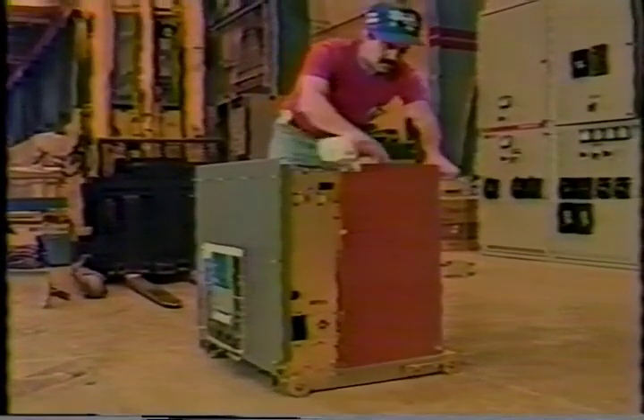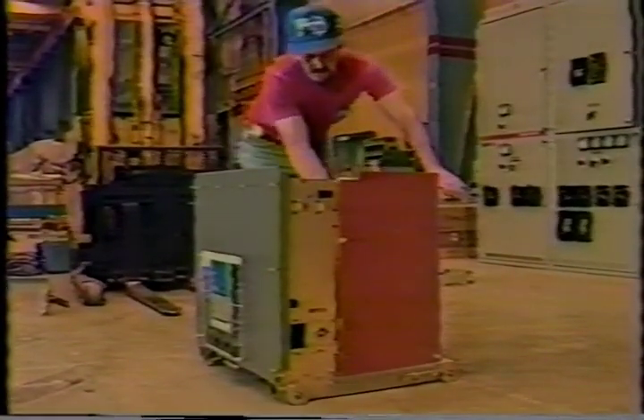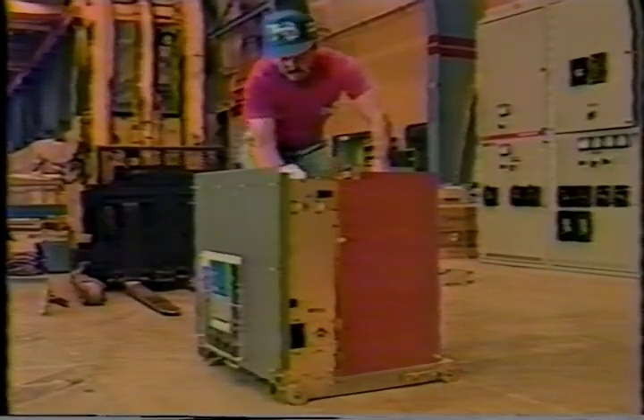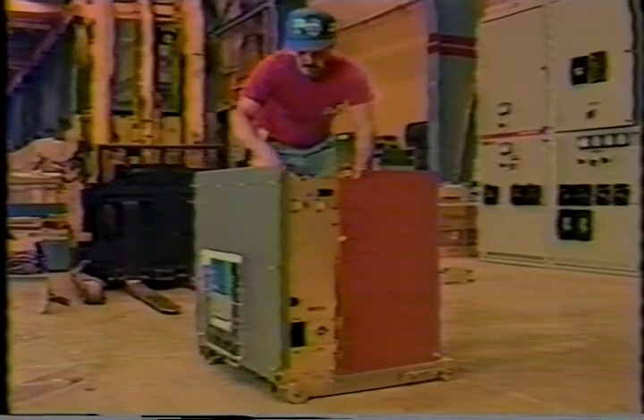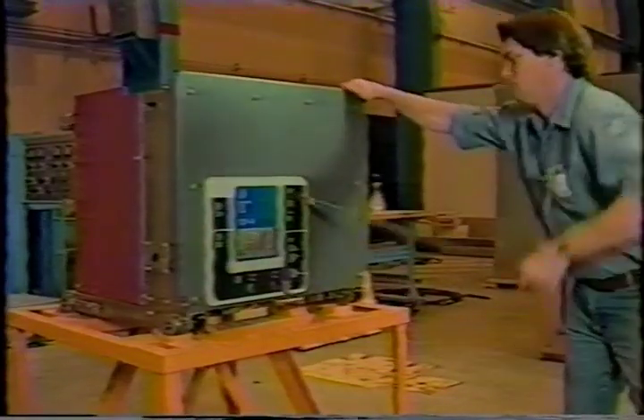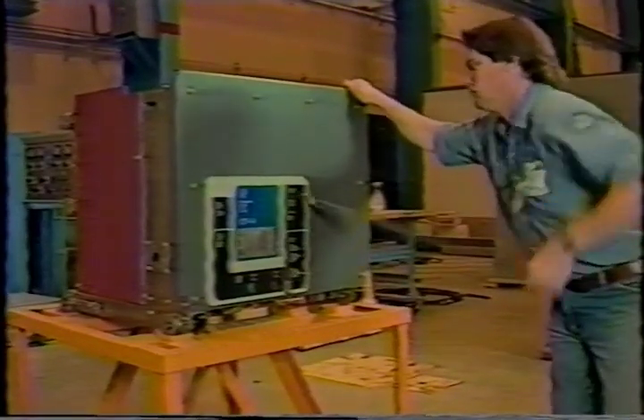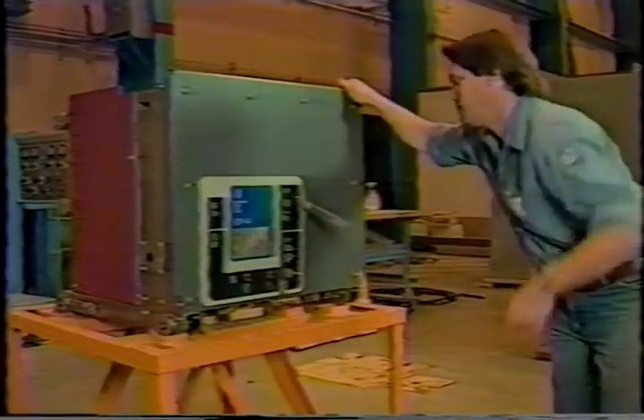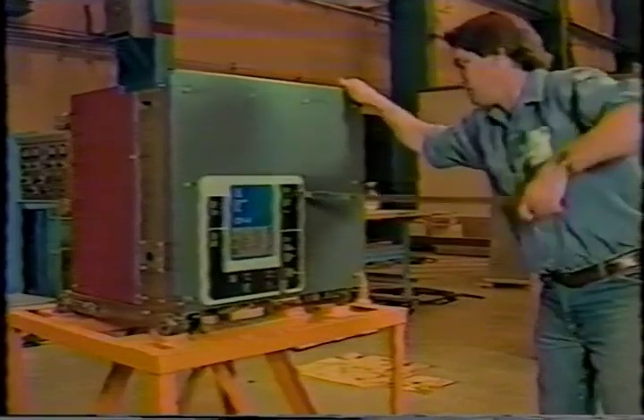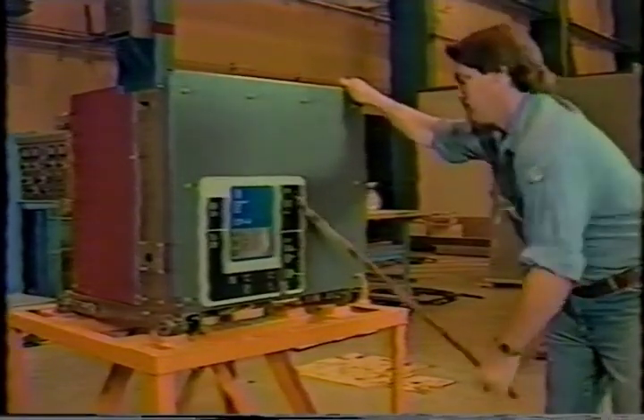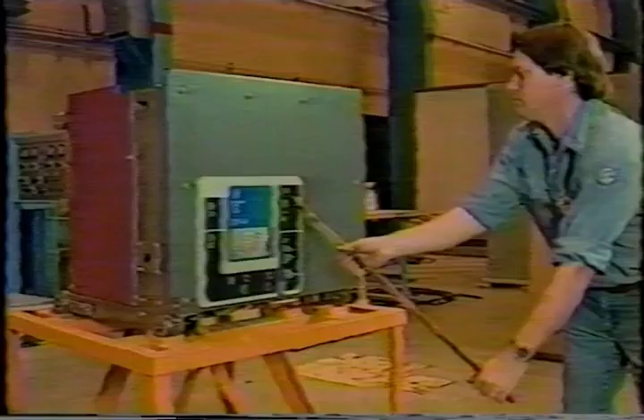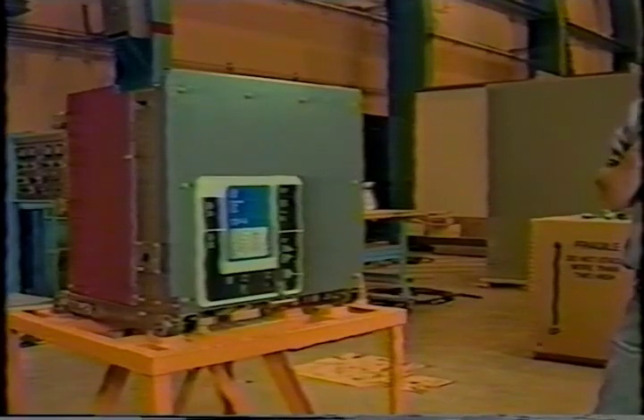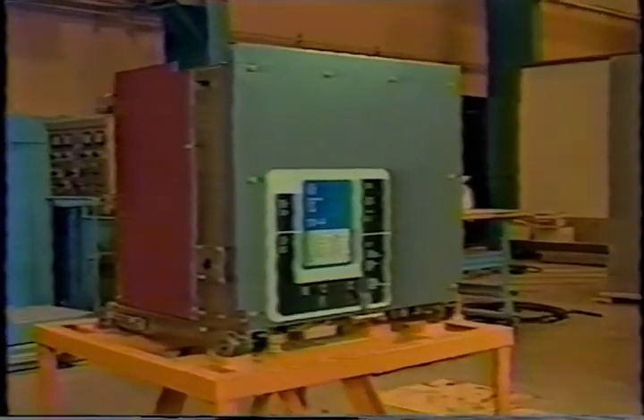Examine each breaker for loose or obviously damaged parts. Before attempting to put the breaker in service, it should be carefully examined and operated manually and electrically. To perform the manual operations, place the maintenance tool in the emergency charge opening and charge the closing spring with up and down strokes of the handle. When charging is complete, the closing crank goes over center and the spring's charged-discharged indicator shows charged. Discontinue charging and remove the maintenance tool as soon as the charged flag is fully visible. Continued attempt to further charge may result in mechanism damage. Close and trip the breaker several times.